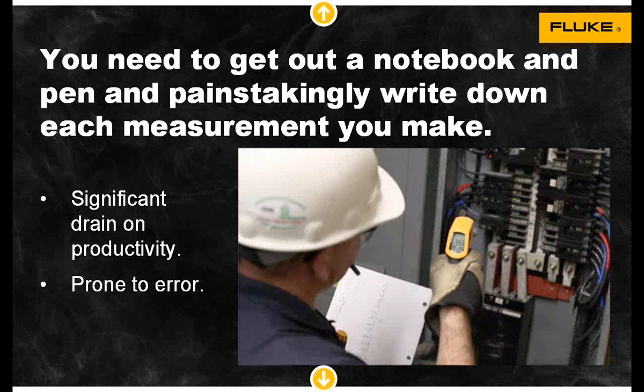You need to get out a notebook and pen and painstakingly write down each measurement you make. Significant drain on productivity. For complex and multiple temperature measurements, this can be very time-consuming. Each individual component needs to be documented in a notebook and each measurement noted down. Generally, faulty components are identified if their temperature is significantly different from other components operating in the same environment. Once all the readings have been documented, the operator has to do the maths to identify the problem. This is prone to error if the operator misidentifies a component or makes an error in his maths.